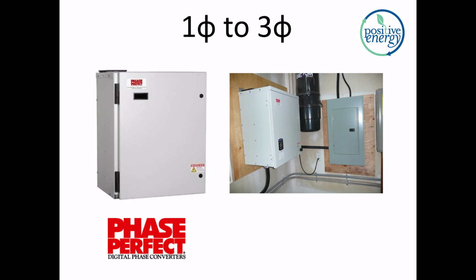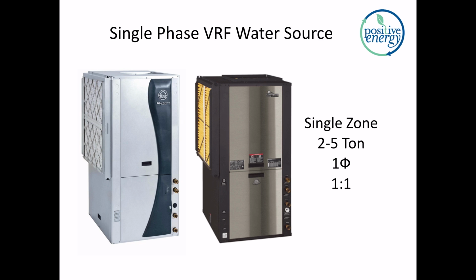It's a little confusing to know that it's been done and yet the manufacturer states, well, we're not sure you're allowed to do it. So either it works or it doesn't, and the manufacturers should decide whether they're okay with it or not. There are single-phase VRF water source systems. Water Furnace 7 Series and Climate Master Trilogy 40 are probably the only two that I know of. There could be others out there, but certainly locally here I've heard of these.